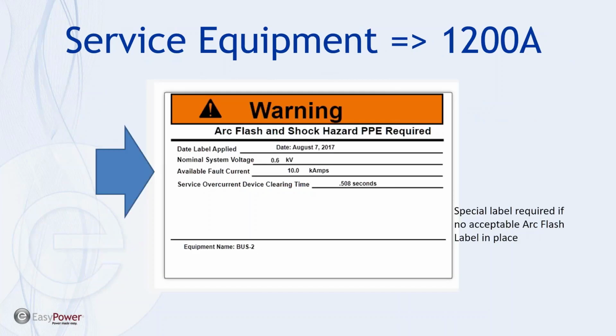It turns out I was working on this hybrid example for the refresher here in a couple weeks, and so I wanted to compare what the results from that project would produce if we had to produce a label for the switchgear. So here's what we're showing. We need to show the date the label was applied, the nominal system voltage, in this case 600 volts, the available fault current, in this case 10,000 amps, and the overcurrent clearing time, indicated at just over half a second, to be more specific.